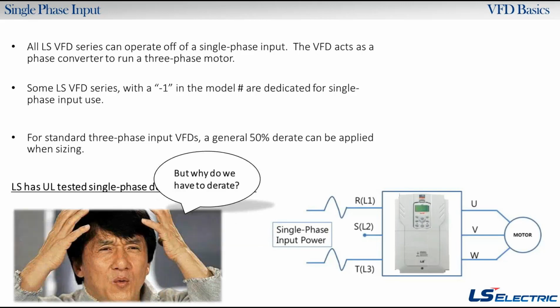So next question, why do we have to derate? It's a good question, Mr. Chan. We have to derate because when we're only running a part of that input, we're not running all three phases, our amperage is going to increase by the square root of 3. That's about 1.73, so almost double. So you're going to have larger capacity wires, you're going to have a bigger breaker on the front end, and the diodes are current rated devices. So you have to oversize the drive to handle the larger current. You're going to have a bigger current on the input for the same amount of current on the output. That's why we have to derate the drive.